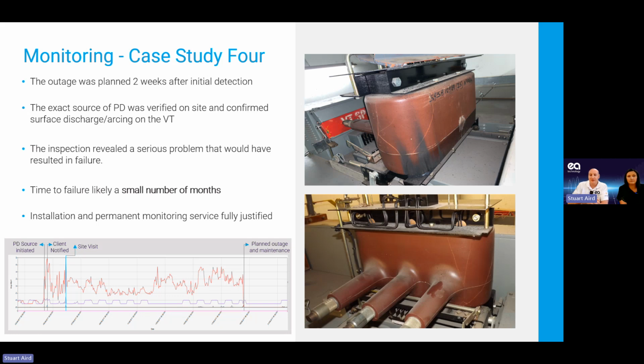So we could go every 6 months. So you've got twice as good a chance of picking up at that time. To get even better, you might want to do it every 3 months. And then that's when the balance between the permanent monitoring solution and the handheld solution starts to line up, because you're using a lot of man hours to do these surveys each time. And the more you do to prevent the failure, the more cost it actually incurs as well. So then you can get to the stage where permanent monitoring is actually a good financial decision.